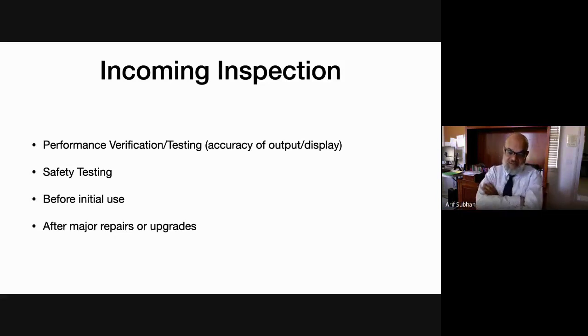It's electrical safety testing, making sure the ground wire resistance is correct, is within tolerance, leakage current testing. Also different mechanical testing for devices that are mechanically inclined, because you don't want the device to in any way harm the patient. And that has to be done before initial use. Before you're using it on the patient, make sure the device is really safe and accurate and providing reliable information.